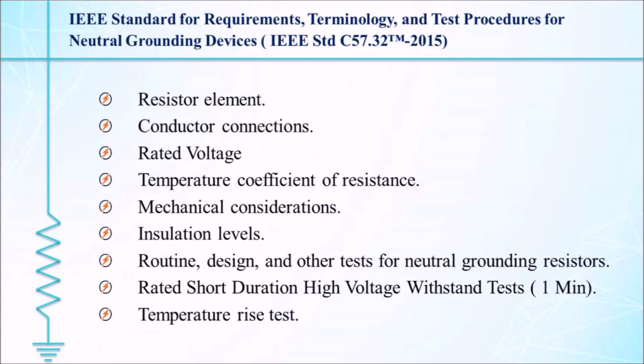Second, conductor connections. All conductor terminations shall be bolted, welded or brazed. A low melting alloy used to join the conductors that will be adversely affected by the resistor operating temperature shall not be used. Third, rated voltage. The resistor shall be rated for the constant voltage and the rated voltage shall be taken equal to the line to neutral voltage. Fourth, temperature coefficient of resistance. The conductor element resistance changes to some extent with the temperature.